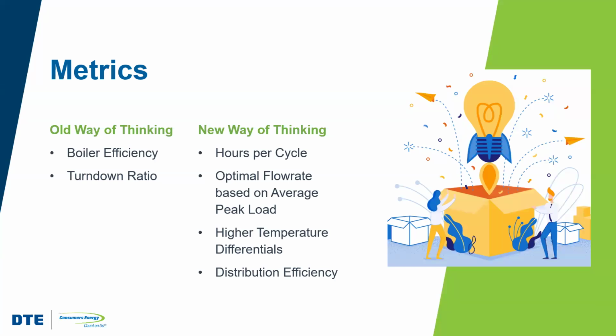We want those boilers to be running longer, right? We don't want the boiler to have a lot of starts and stops. So that hours per cycle, that's an important number. Right? We want it to be bigger than it has been in the past, right? Because the boilers are operating more efficiently when they're operating at their steady state point.